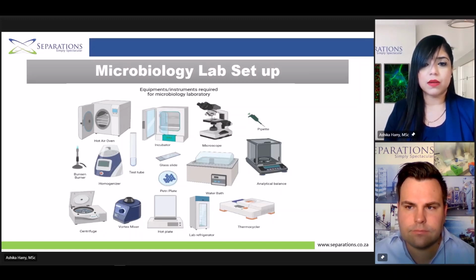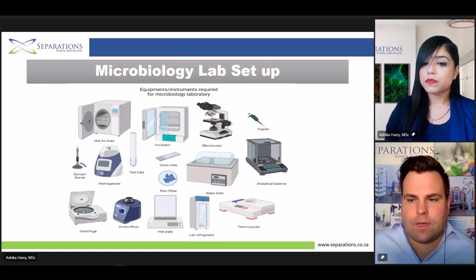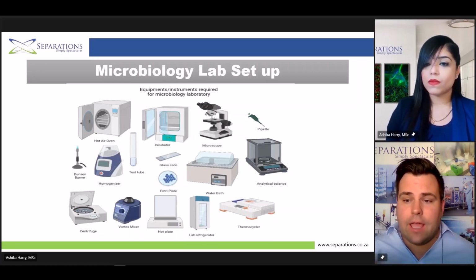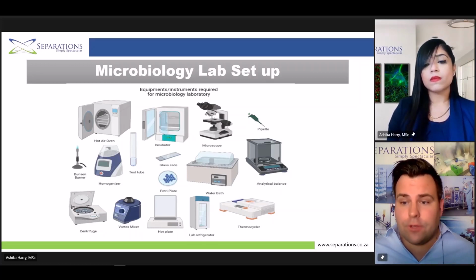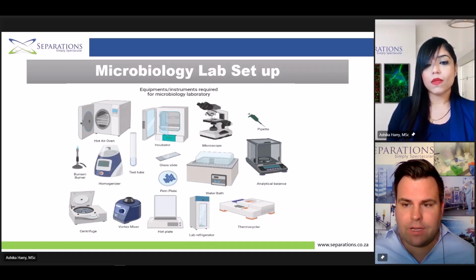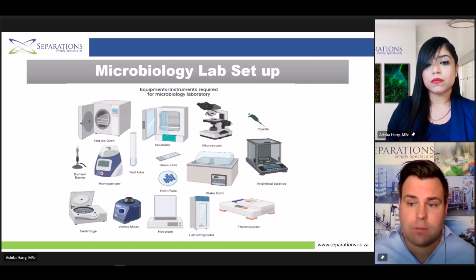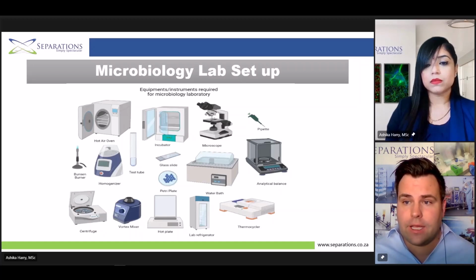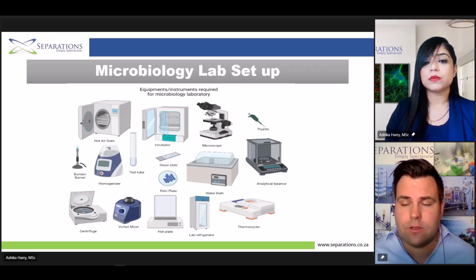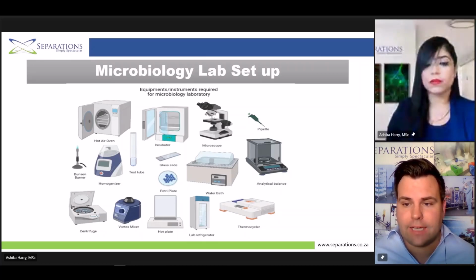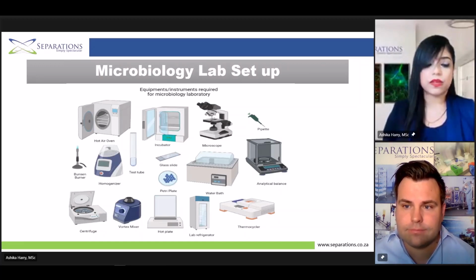with your microbiological samples. Yeah, and I'll jump in there quickly because sometimes with a laminar airflow and a microbiological cabinet, there's a confusion. If you're not dealing with anything hazardous and it's just routine analysis, a laminar airflow is fine because it's just basically pushing air out, including to the operator. So if you're just worried about sterility and you're not worried about anything hazardous in that lab, that's where you use the laminar airflow. And exactly, when you're dealing with something that could pose a risk, that's where you have that microbiological safety cabinet. Yes, Jeff, that's right.